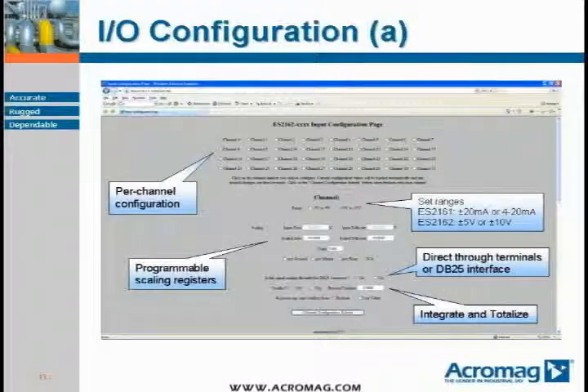Per channel configuration allows independent customization of each channel's input and output parameters. Each channel allows the input range to be set at plus or minus 20 mA or 4 to 20 mA for the ES2161 and plus or minus 5 or 10 volts for the 2162. Each channel may also be scaled independently and have integration totalization turned on.